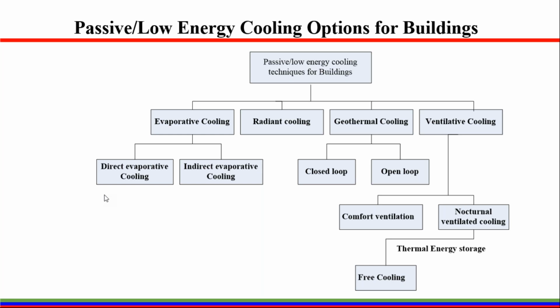Ventilative cooling means during the night time when the ambient temperature drops. For example, in such areas, the daytime temperature can be 40 degrees centigrade and the nighttime can be 20. Then we can use the ventilative cooling in that case.